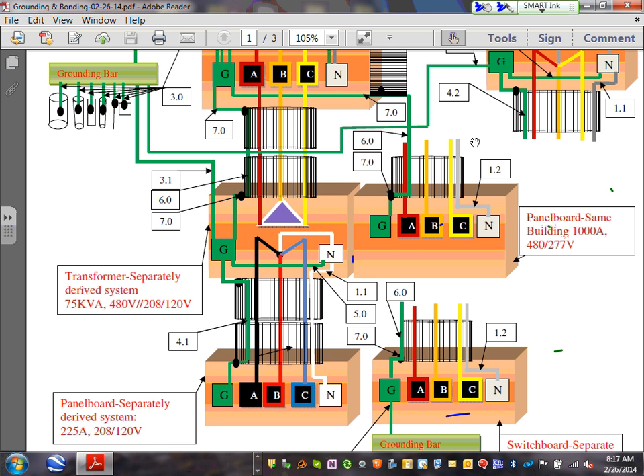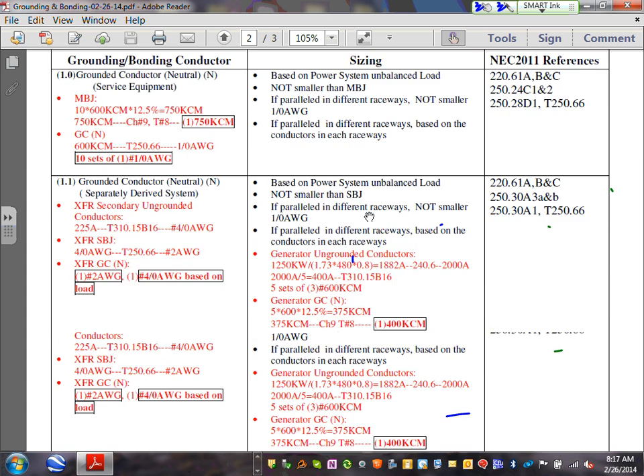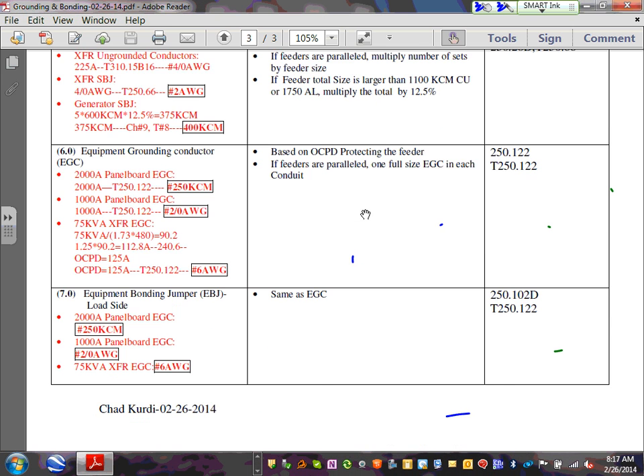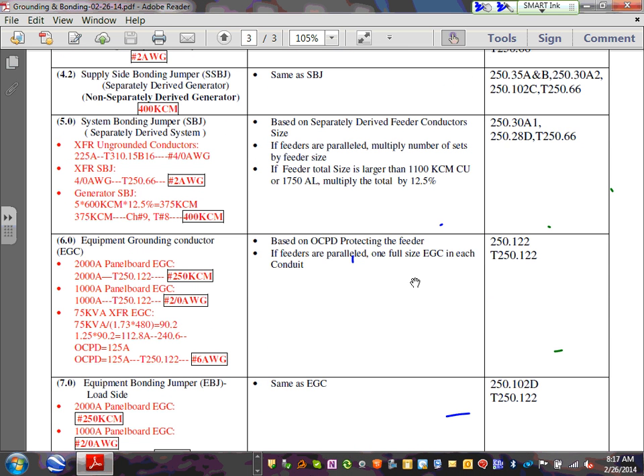No need for a conductor. If your conduit here is PVC, then you have to pull an equipment grounding conductor with it. If it's an EMT conduit, guys, you also have to pull an equipment grounding conductor, and you need to bond the conduit. So do me a favor, let's go to 6 and 7, will you? So if you guys go to number 6 right here, Karen, it says equipment grounding conductor.